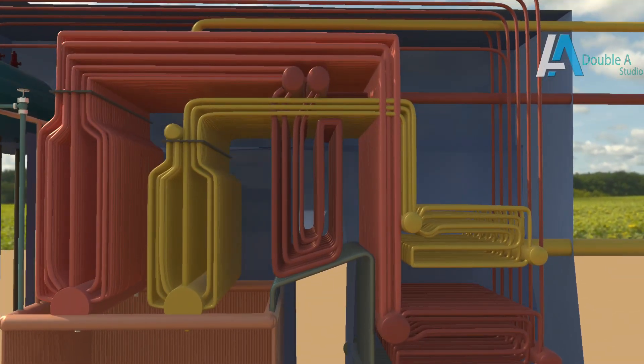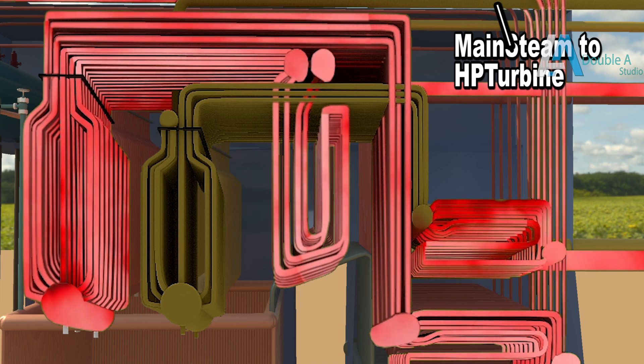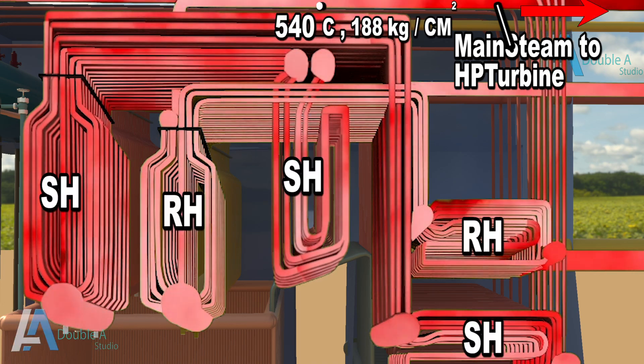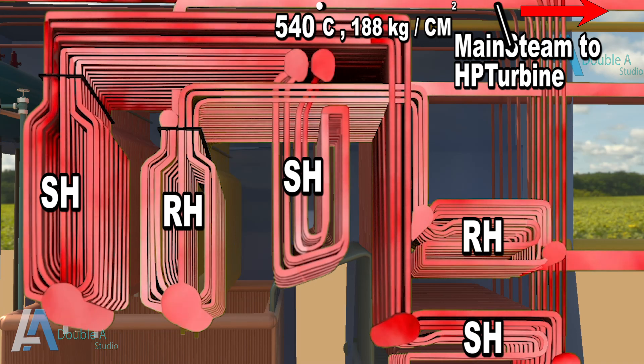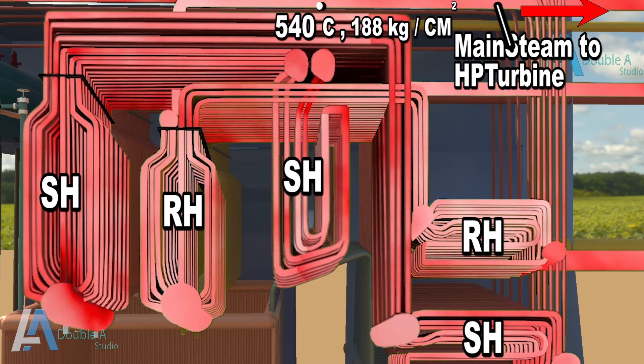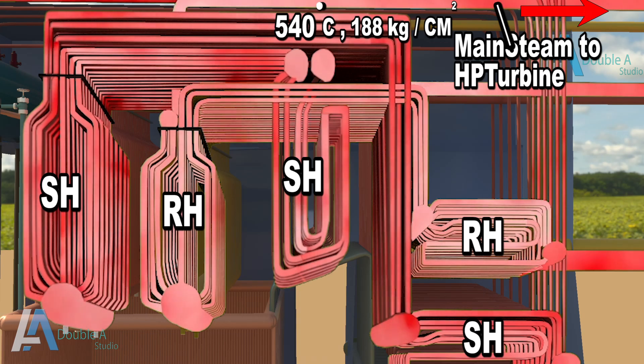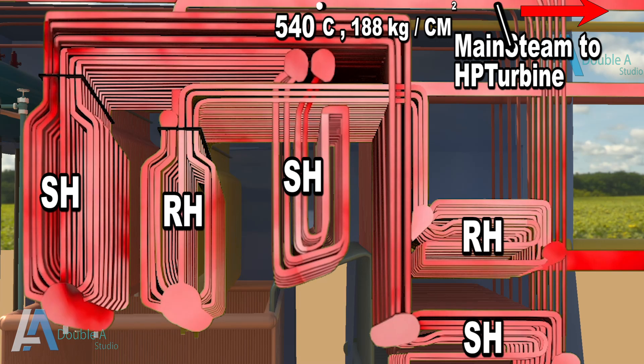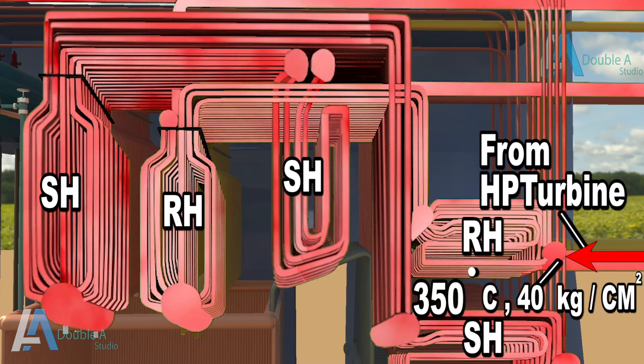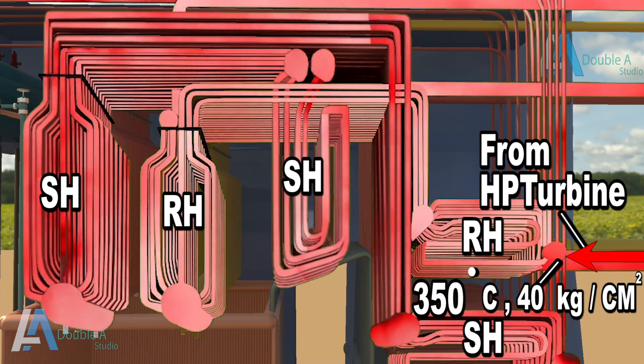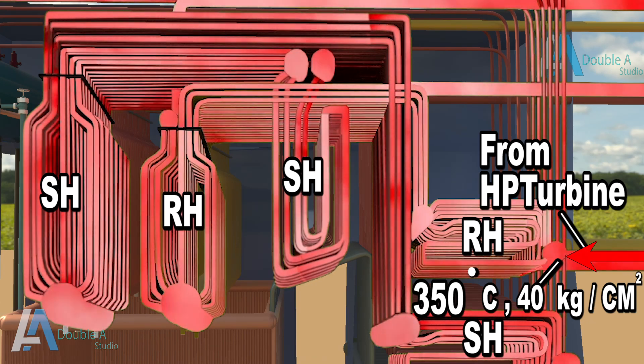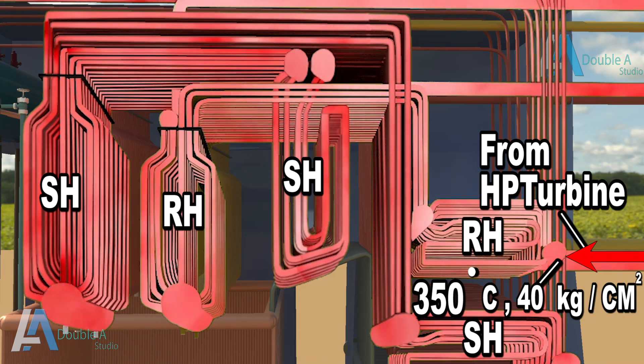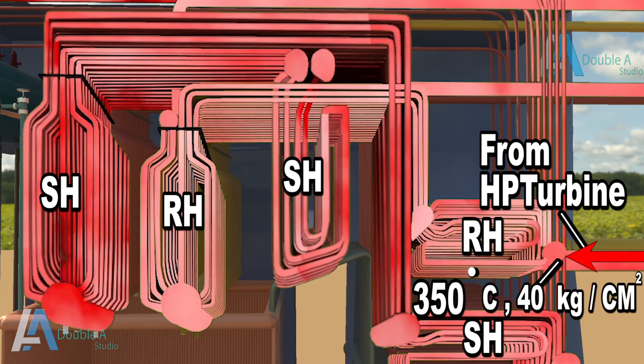To understand this process, let's recall superheated steam coming out of final superheater. This is also called main steam having temperature of 540 degrees centigrade and pressure of 188 kilogram per centimeter square. It enters HP turbine and expands there. Expansion of steam reduces its temperature and pressure to about 350 degrees and 40 kilogram per centimeter square respectively. These figures are indicative and will vary depending upon type and size of thermal plants setup.